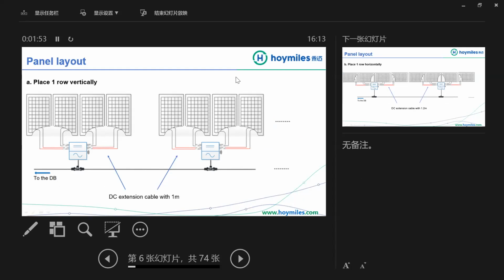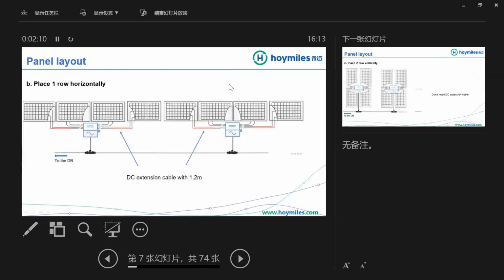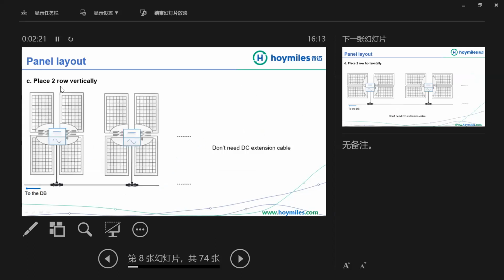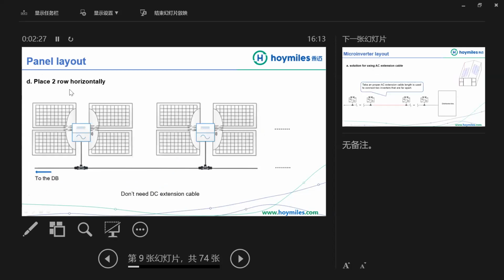When you install the microinverters, there are actually 4 methods for panel layout you could choose. First one is place one row vertically, but need 1 meter DC extension cable for use on the further panels. Second is place one row horizontally, but need 1.2 meters DC extension cable used on the further panels. The last 2 methods are place 2 rows vertically or place 2 rows horizontally. These 2 methods don't need any more DC extension cable.